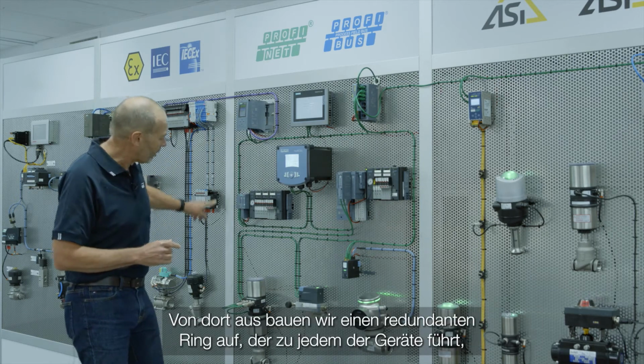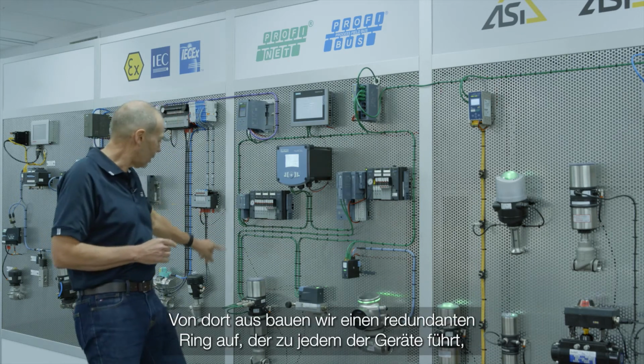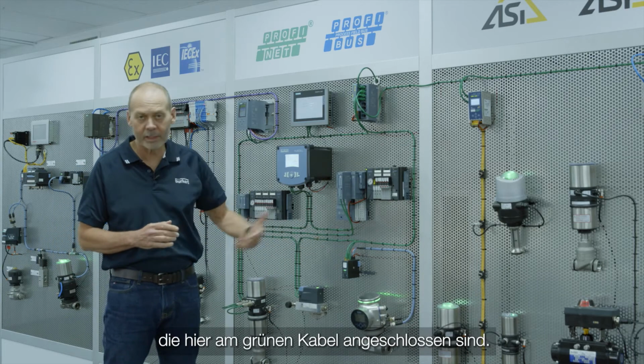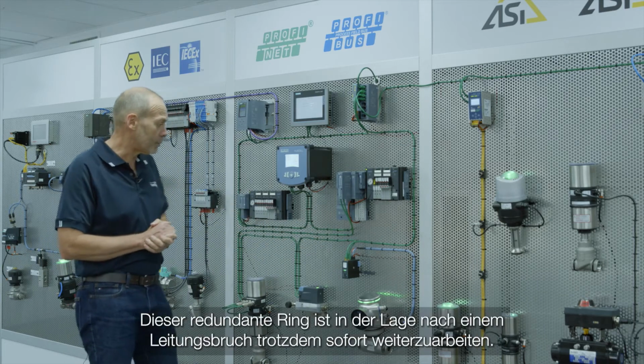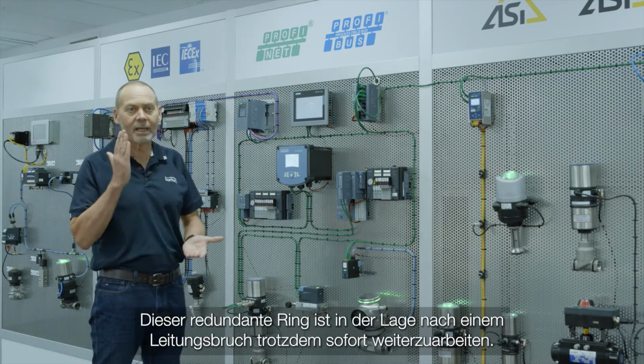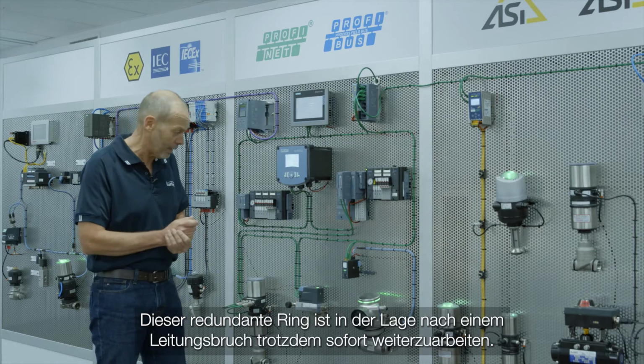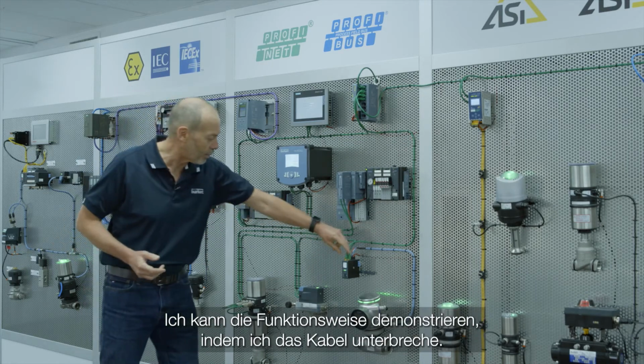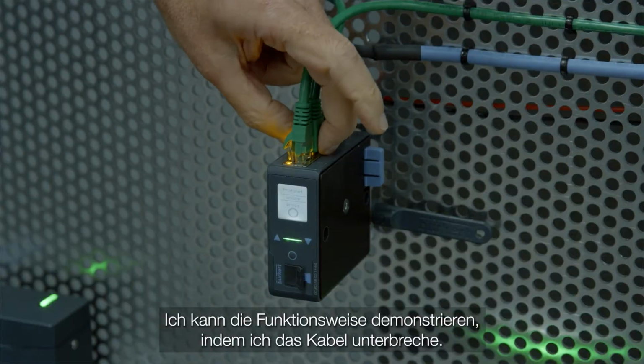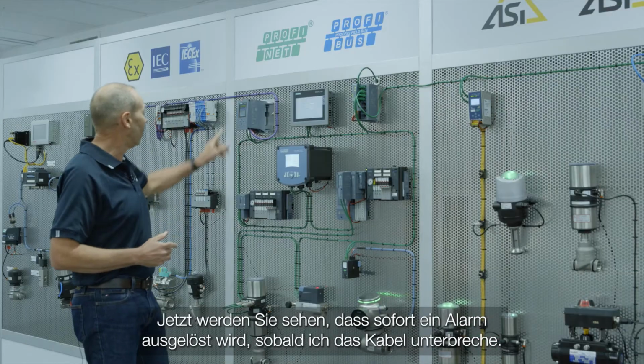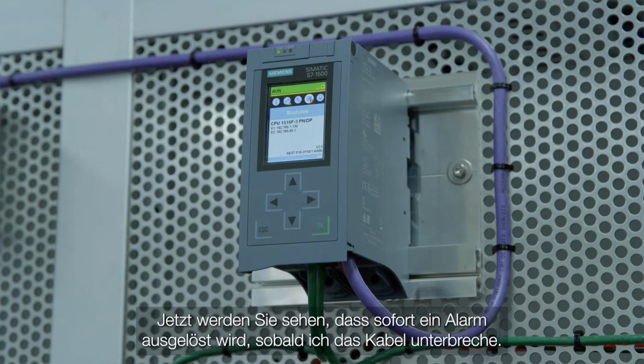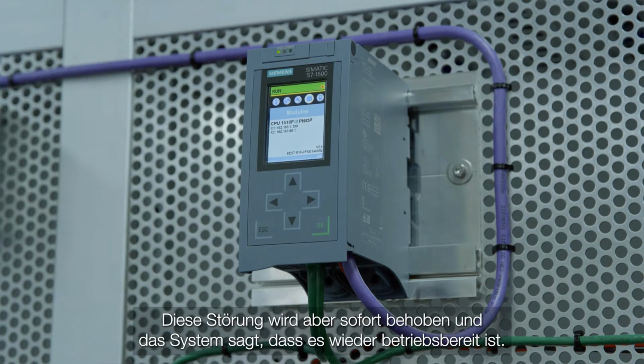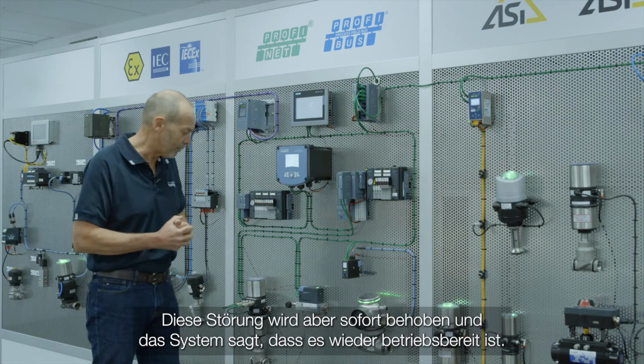From there, we're setting up a redundant ring that goes around each of the devices that are installed here on the green cable. This redundant ring has the ability to accept a cable break and yet pick up immediately. I can demonstrate the operation of this by literally breaking the cable. Now you'll see that we get an alarm immediately that I've broken that cable, but it does come good immediately and says I'm back up and running.